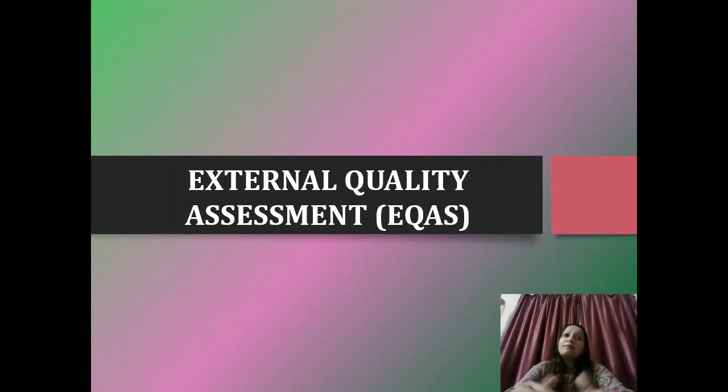Apart from this, we can go through other processes like verifying the measurement range, the entire range across which our examinations are valid. Say our machine has a measuring range of 5 to 700 milligram per dL for blood glucose. Whether the machine is actually able to report to that extent, I have discussed in the previous module, so far as linearity checks were concerned, where we dilute the patient sample and see to what extent the diluted values can be reliably given by the lab instrument.